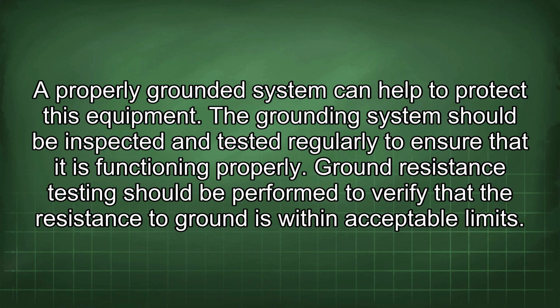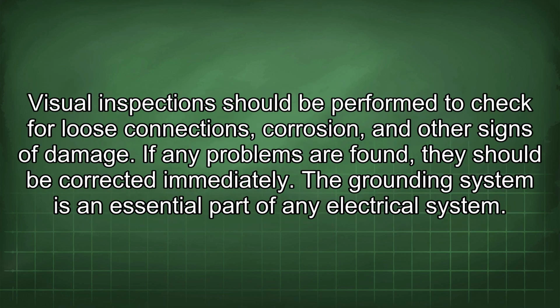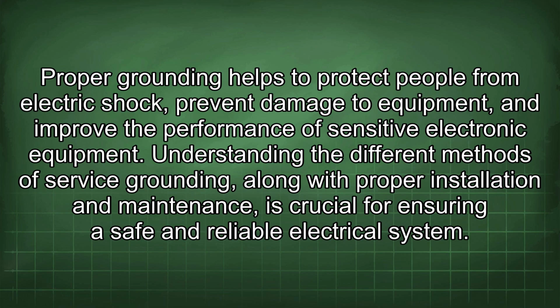The grounding system should be inspected and tested regularly to ensure that it is functioning properly. Ground resistance testing should be performed to verify that the resistance to ground is within acceptable limits. Visual inspections should be performed to check for loose connections, corrosion, and other signs of damage. If any problems are found, they should be corrected immediately. The grounding system is an essential part of any electrical system. Proper grounding helps to protect people from electric shock, prevent damage to equipment, and improve the performance of sensitive electronic equipment.